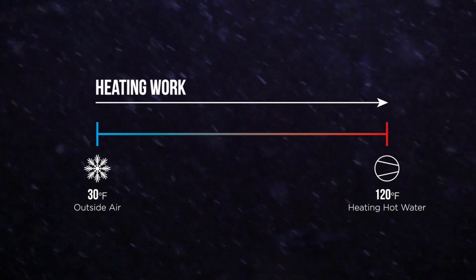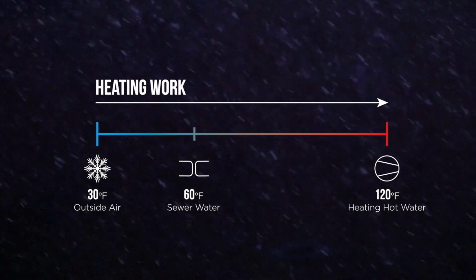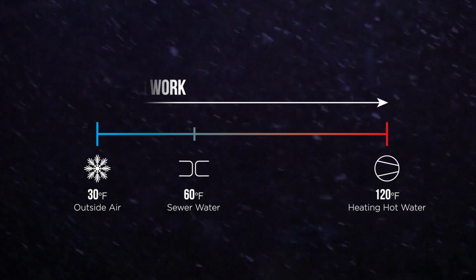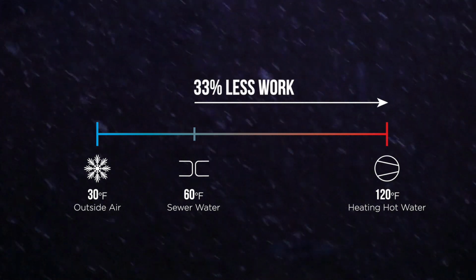We can use wastewater to more efficiently heat and cool buildings. People laugh at me when I say that, but it's true. Every drop of water that goes down the drain can be used to make HVAC more efficient. The idea is a lot like geothermal systems, which you might have heard of, used in less densely populated areas. Just like the soil deep underground, wastewater in the sewers is actually fairly constant temperature year-round. So when it's freezing outside, since the wastewater is warmer than the outside air temperature, we can use it to run our heating systems more efficiently.